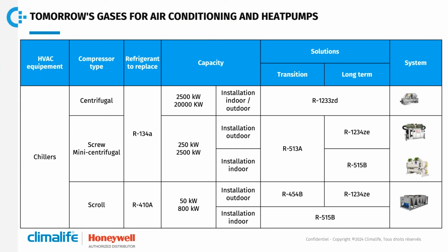In scroll applications, to replace R410A, the transition solution if the system is outside is R454B, and for the long term, we have again R1234ze. If we have the system inside, we have R515B. The interest of R515B is the low GWP, 288, interesting to preserve quota, and it's a non-flammable product, A1 classification, so easy to use in all cases, with the same capacity as R1234ze.